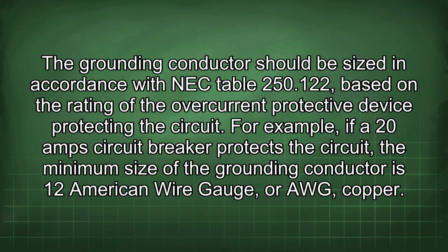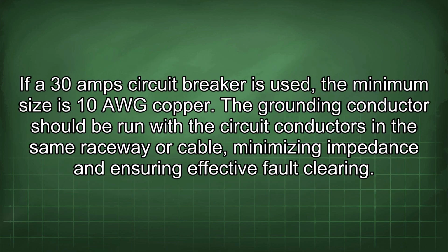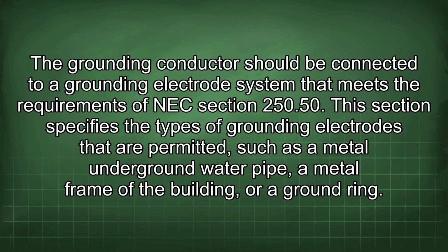For example, if a 20 amp circuit breaker protects the circuit, the minimum size of the grounding conductor is 12 American wire gauge, or AWG, copper. If a 30 amp circuit breaker is used, the minimum size is 10 AWG copper. The grounding conductor should be run with the circuit conductors in the same raceway or cable, minimizing impedance and ensuring effective fault clearing.